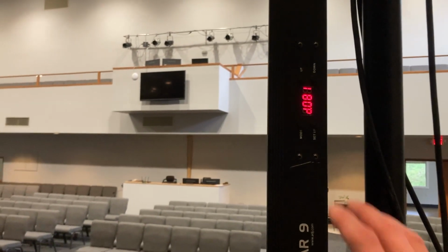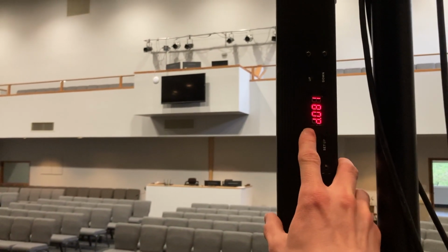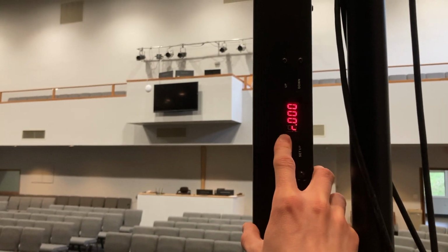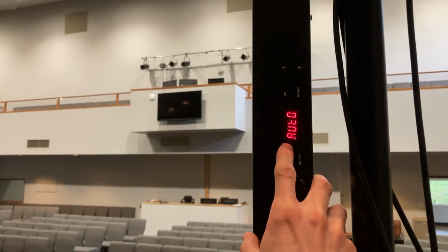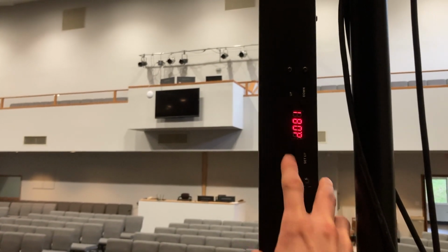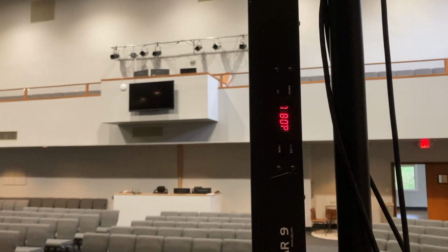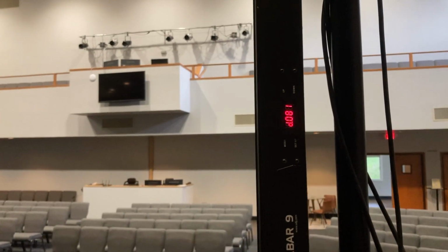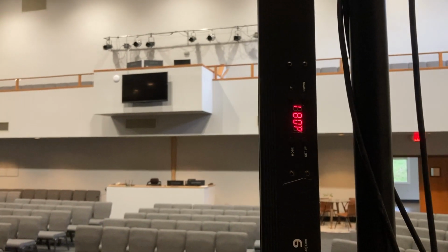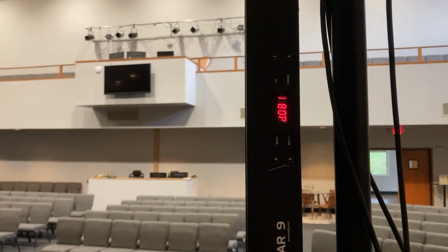So to adjust that, you can just press the mode button right here. I can change that to a particular color, set to a particular shade, or some of these other settings which we never use, but we want to make sure it's set to DMX, and for this light, 81, that's the right channel that it should be set to. And so that's how to troubleshoot anything here on the stage.